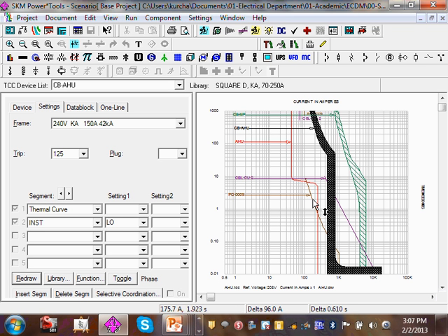So when you pick a circuit breaker, you're going to pick the circuit breaker based on the trip unit, the trip value, which is that value right here, and the high short circuit here, to match the available short circuit to your system. So let me change this circuit breaker, guys, into a different circuit breaker if I can. Here's my options in this series. And my option is I can go 110.